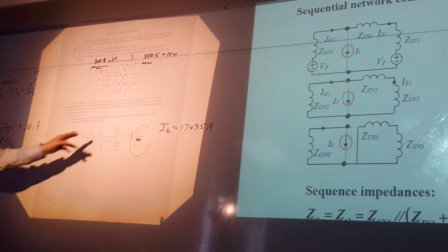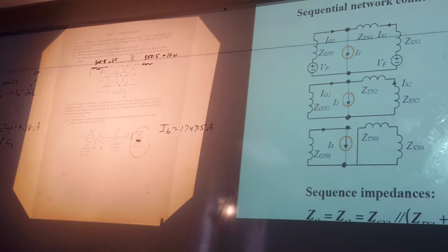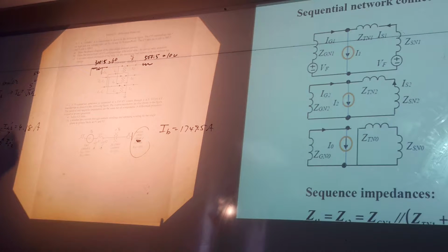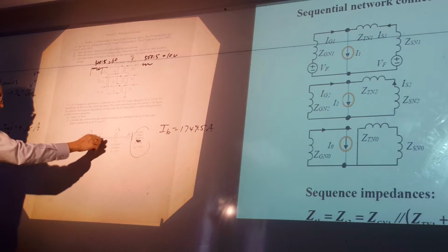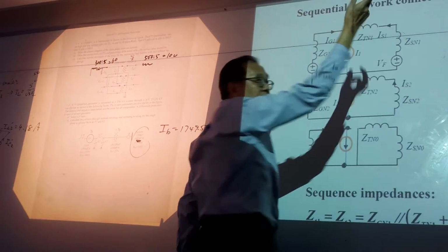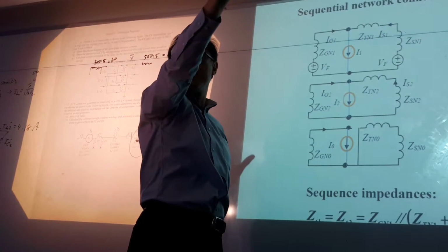This is the internal fault, to the left of the CT. To the right of the CT is an external fault. Because we say internal is whatever is protected under this zone, including a little bit here and the generator winding and a little bit here. This one will be external, but as far as the circuit is concerned, the CT has 0 ohm. So internal or external here is only this point because the CT is here. CT has 0 ohm, so we don't consider it.